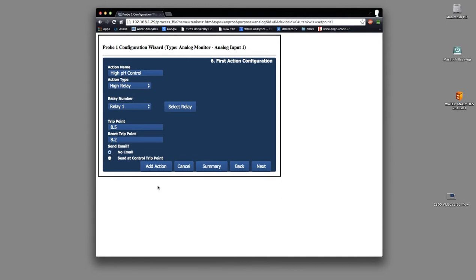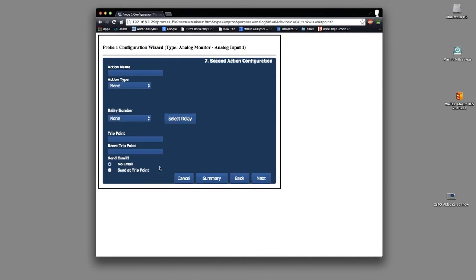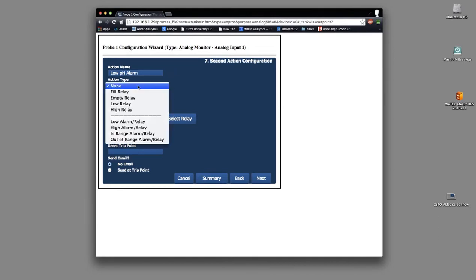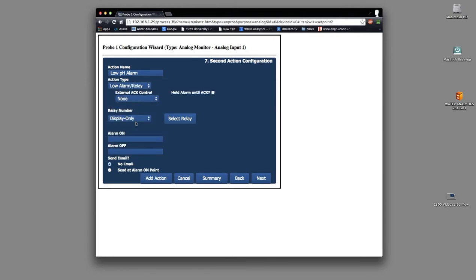Now let's add an alarm that activates if the pH goes too low. I'm going to click on the button Add Action to repeat the setup process. I'll call this action Low pH Alarm. For action type, I'll choose Low Alarm / Relay, which means that I can add a relay that will also activate in addition to the alarm when the pH dips too low, but I'll decline to, since there is no pump to dispense a caustic solution. So I'm going to leave the relay number at display only, which is to say no relay.